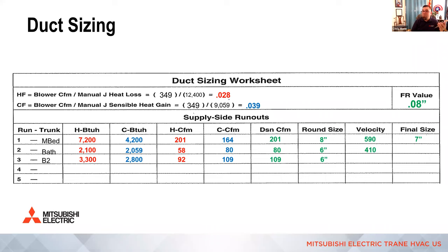We want to make sure that the air is not moving too slow or too fast. You can see in this example, the 6-inch ends up being really low, 410 feet per minute. So we actually have to downsize that to a 5 for the bathroom. And then the second bedroom, we could downsize, but we shouldn't, because if we go to 5 inches and we're putting 109 CFM through that, unfortunately the feet per minute is too high. It's over 900. So we stick to the lower number in that example because we don't want a noisy second bedroom when that thing cranks up. So that is how you size the runs.